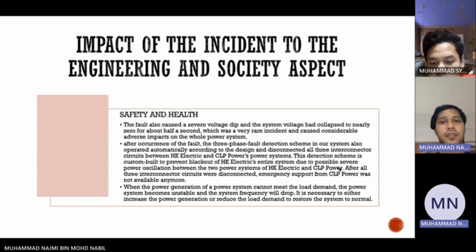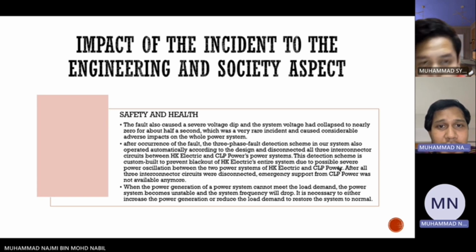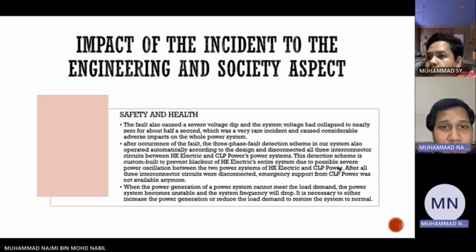So, the impact of the incident on the engineering and society aspect. For safety and health, the fault also caused a severe voltage dip, and the system voltage collapsed to nearly zero for about half a second, which was a very rare incident and caused considerable adverse impact on the whole power system. After the occurrence of the fault, the three-phase fault detection scheme in our system also operated automatically according to the design and disconnected all three interconnector circuits between HK Electric and the CLP power system. This detection scheme is custom built to prevent blackout of HK Electric's entire system due to possible severe power oscillation between the two power systems of HK Electric and CLP Power.